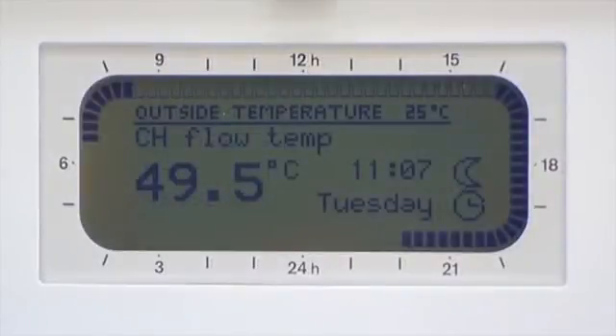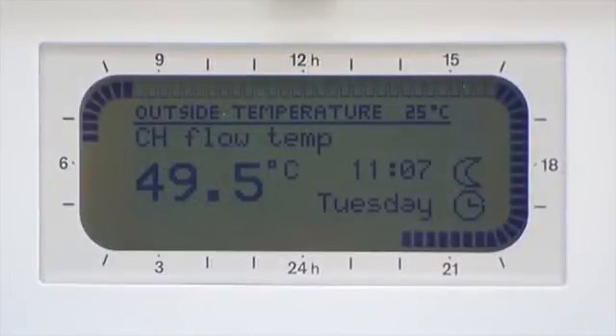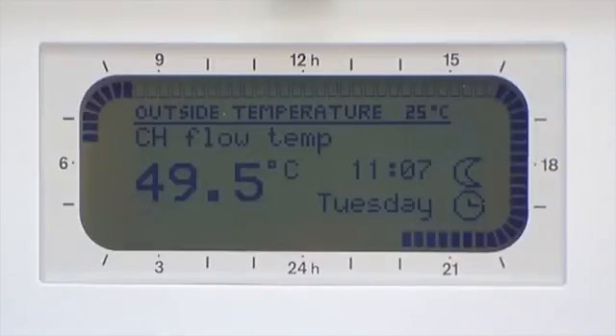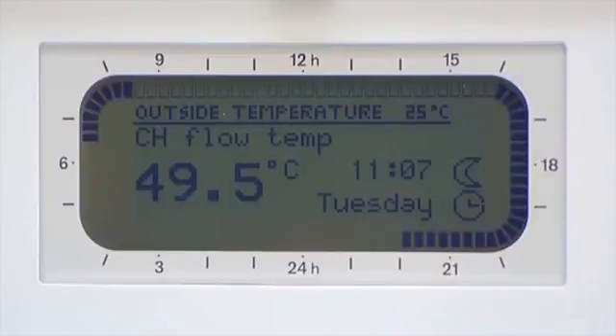Once you've set your programme, you're able to do a quick visual inspection to see that your settings have been accepted. Around the outside of the display you will see a 24-hour clock, rather like a traditional mechanical timer. Each section is in a 15-minute block. A filled-in block indicates the heating is set to come on — i.e. Comfort setting. A block which is outlined only indicates an Economy setting, and no block indicates a Frost setting.